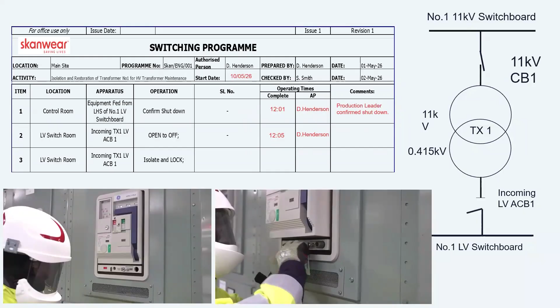So in this example, I'm using a caution sign, which is warning against interference, because I don't want anybody trying to close that back in whilst I'm working on the network. It could be your example. You might use a do not operate tag. You might have your own specific tags. But in this example, I'm going to use a safety lock. So it's unique with one key. And I've got a caution notice warning against interference. And then I'll update my switching program to confirm that it's been done. You can track the safety lock number if you like. I like to do it just so I know which key I'm getting when I'm doing the restoration.